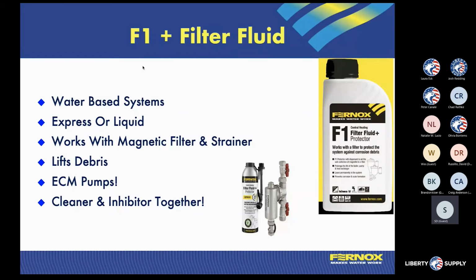So now we have a system that is broken down, but we can't have it be down. We will install a magnetic filter that has a strainer built into it, or a separate strainer. We will add our F1 and filter fluid, and now we're going to use that strainer and that magnetic filter to remove the dirt and sediment. It'll also be our replenishment point, because we're going to drain that magnetic filter down. That's going to be our replenishment point to add more inhibitor into that system.